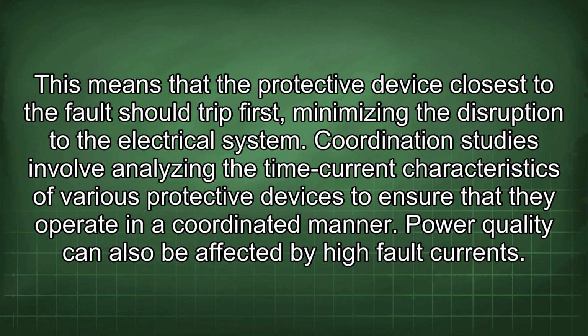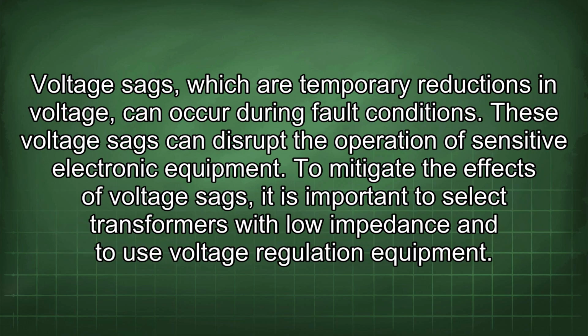Power quality can also be affected by high fault currents. Voltage sags, which are temporary reductions in voltage, can occur during fault conditions. These voltage sags can disrupt the operation of sensitive electronic equipment. To mitigate the effects of voltage sags, it is important to select transformers with low impedance and to use voltage regulation equipment.